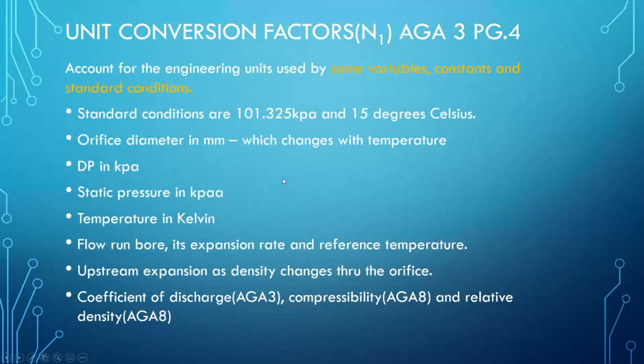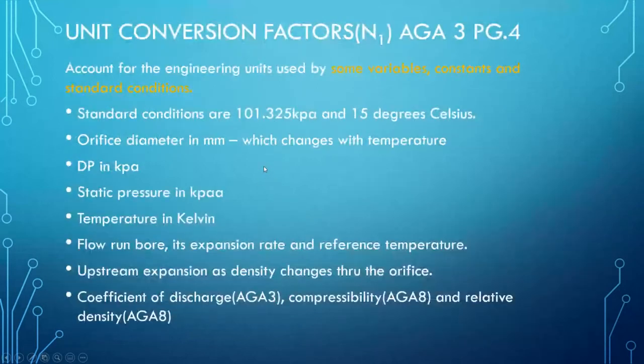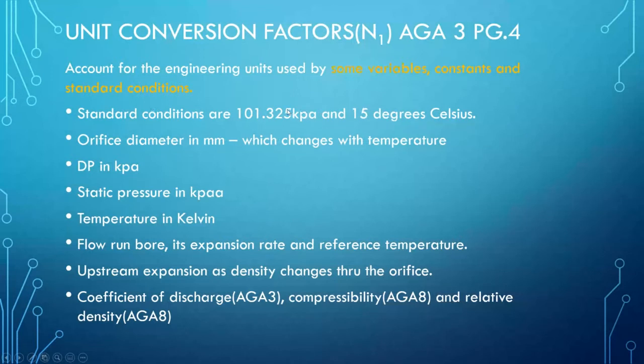Unit conversion factors are a significant topic in the ILM. The N1 variable is the unit conversion factor, and its purpose is to account for the engineering units used by various constants and standard conditions. Standard conditions are typically 101.325 kPa and 15 degrees Celsius when doing flow measurements.